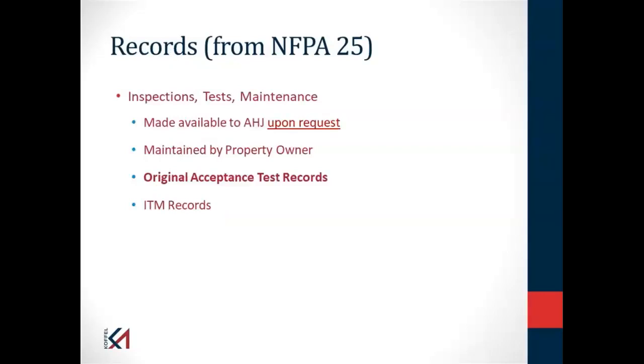Record keeping is a big issue with inspection, test, and maintenance of systems. As one who does expert witness work, if there's a problem with a system, one of the first things I ask for are all the inspection, test, and maintenance records. Notice I bolded one bullet: you're supposed to have the original acceptance test record.